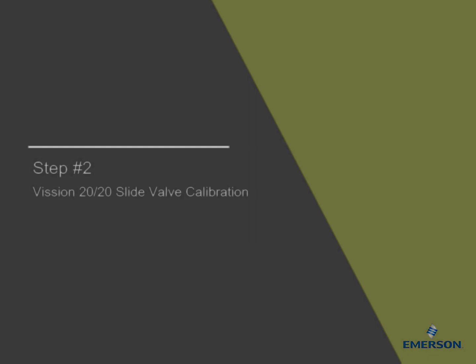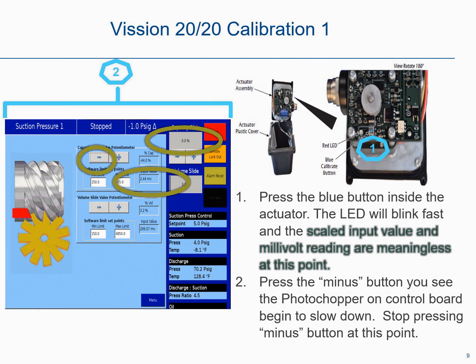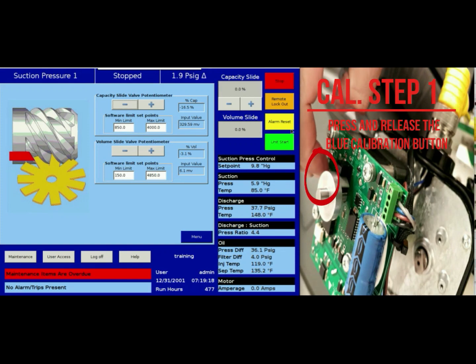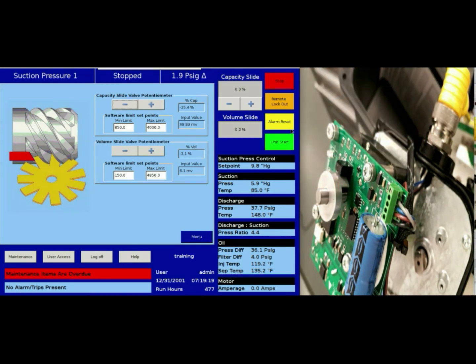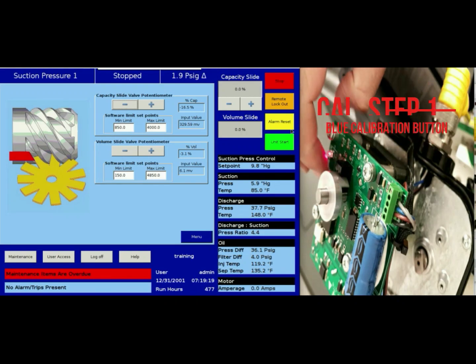Vission 20/20 Slide Valve Calibration. Once in the slide valve calibration screen, you'll need to press the blue Calibrate button inside the actuator to commence the slide valve calibration process. To do so, remove the 4 screws on the actuator that you would like to calibrate. Then press the blue Calibrate button one time. Please keep in mind that the actuators cannot be calibrated in direct sunlight. Provide shade when the cover is removed.